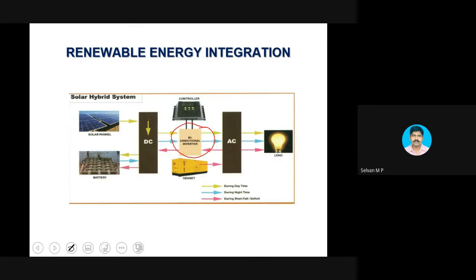So when you purchase an inverter, if you want off-grid operation, then you have to think twice and look into the design and the specifications. The inverter which needs to work in both on-grid and off-grid mode will be a little expensive, because in off-grid mode you have to generate your own reference and make it work. In on-grid mode, it will take its reference from the grid voltage.